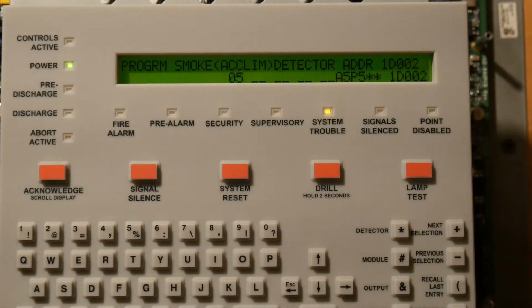But while we're waiting for that, as I was saying, when you're going to auto program mode, there should be four bell circuits, because your four bell circuits are your NACs. If there aren't four bell circuits, something's wrong with your panel and you should get it checked out. As for everything else, if you have something installed and there isn't at least one module or at least one detector, there could be one module and zero detectors or one detector and zero modules. If there isn't at least one addressable device on the SLC, your SLC is probably dead.